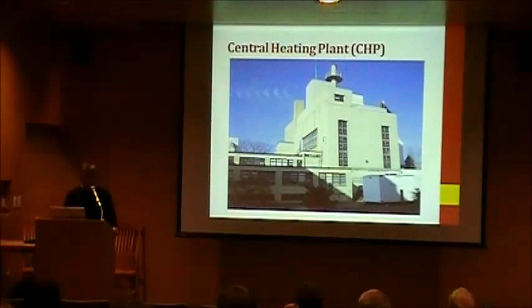We have two coal-fired boilers, which are solid fuel boilers, on the east side of the building, and one natural gas boiler on the west side. The maximum steam required on average for heating the campus is approximately 65 to 70,000 pounds per hour. Along with this, we have a 375 kilowatt co-generator.